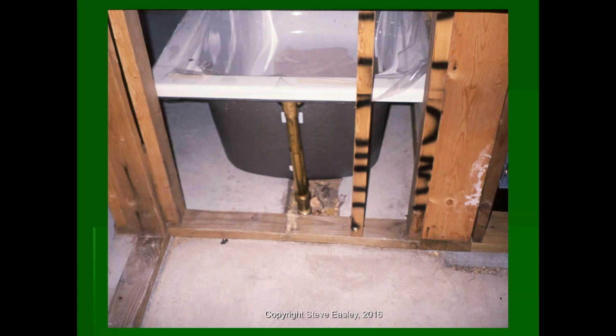This is a project that I looked at in the Chicago area where they did not seal underneath the slabs. They had a little bit of an issue with water running underneath the slabs, and so every time the HVAC system turned on, people would smell mold in these duplexes. And the reason is that the ductwork had quite a bit of duct leakage, so it put the home under negative pressure. So guess what?